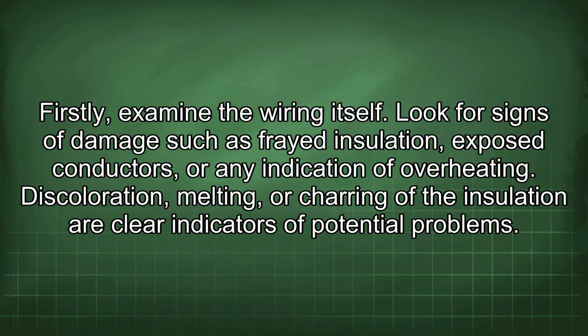Firstly, examine the wiring itself. Look for signs of damage such as frayed insulation, exposed conductors, or any indication of overheating. Discoloration, melting, or charring of the insulation are clear indicators of potential problems.